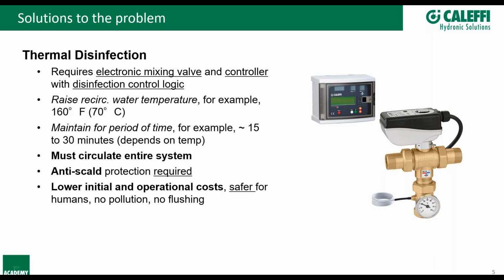With our particular product here, we also have the ability to verify that the thermal disinfection cycle has been completed, with the use of a sensor on the recirc return. Basically, with that sensor we're looking for a specific temperature for a specific duration of time, and that's something we can use to confirm that you actually completed that thermal disinfection process.